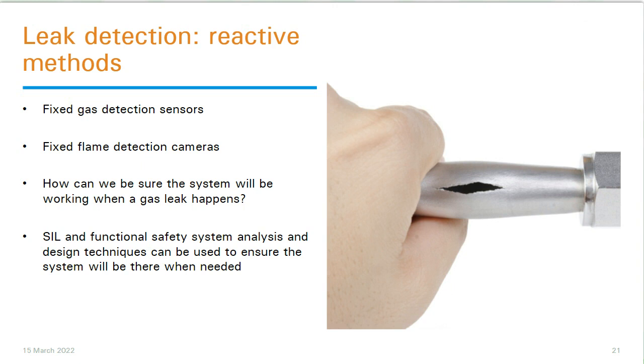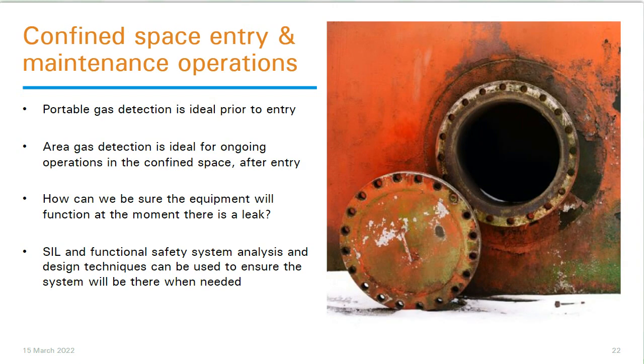If we ask what's the appropriate gas and flame detection equipment for confined space entry or maintenance operations inside a tank where there may be toxic chemicals or nitrogen and inert asphyxiant gas, well, portable gas detection is ideal to check prior to entry, and area gas detection inside of that confined space would be ideal to have close to the operators, close to the maintenance team during their work inside the confined space. So a mixture of equipment is ideal for confined space entry and maintenance inside confined spaces.